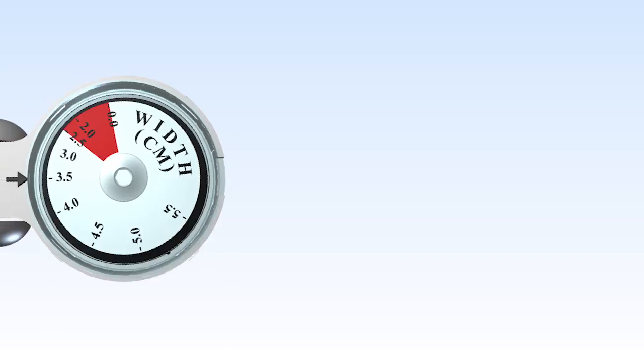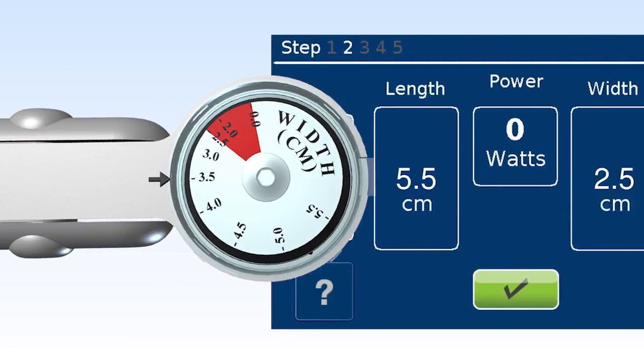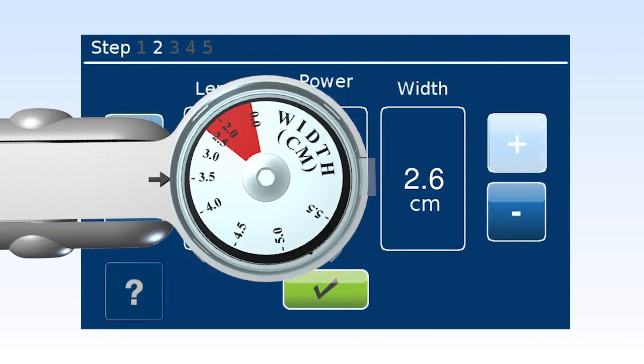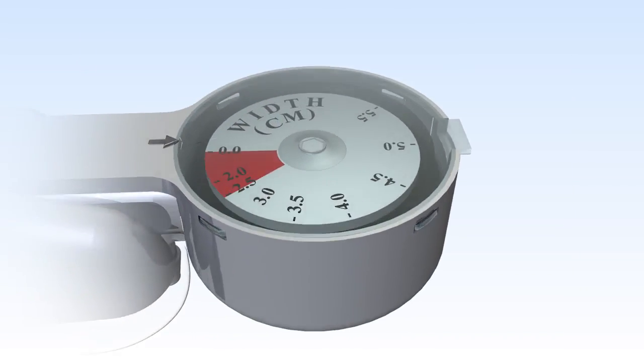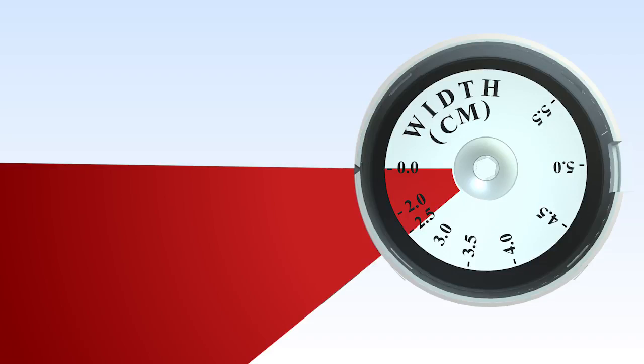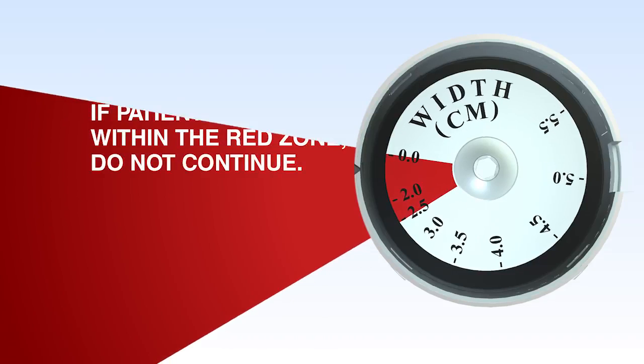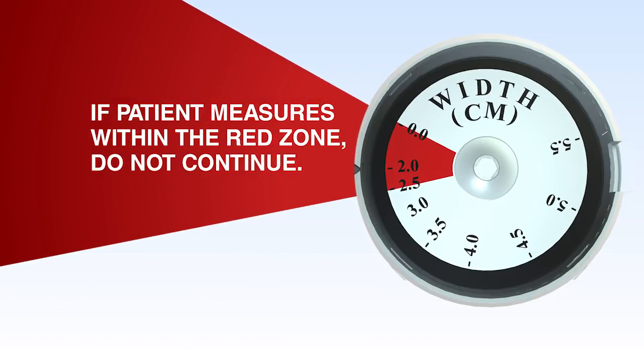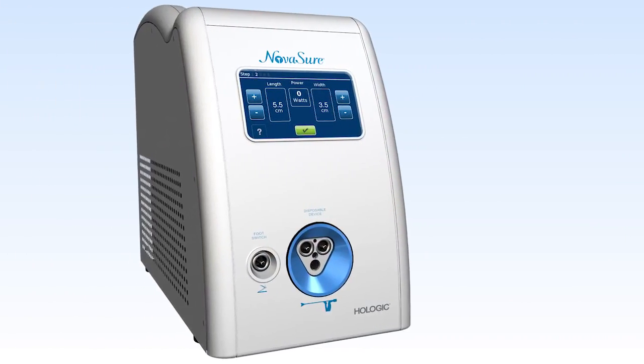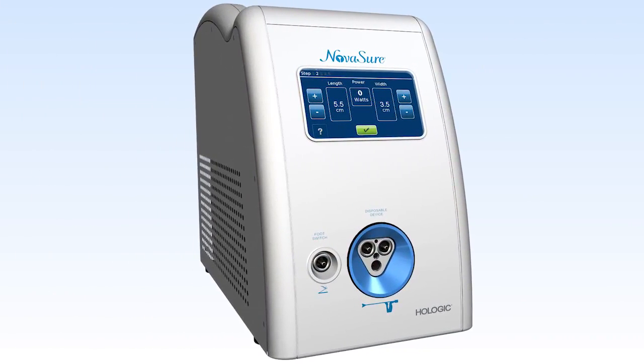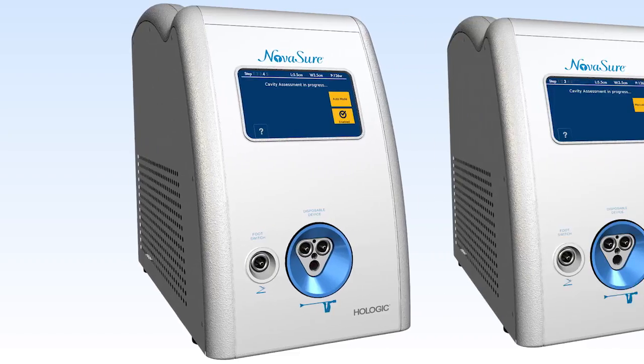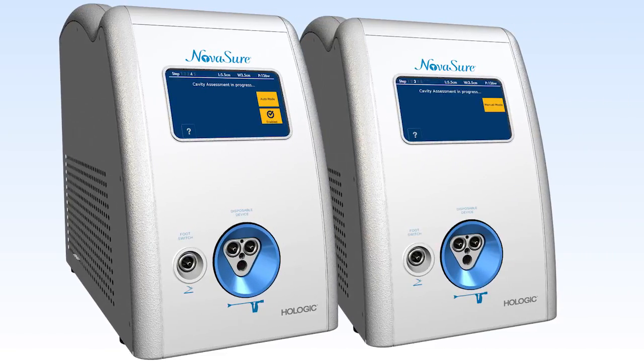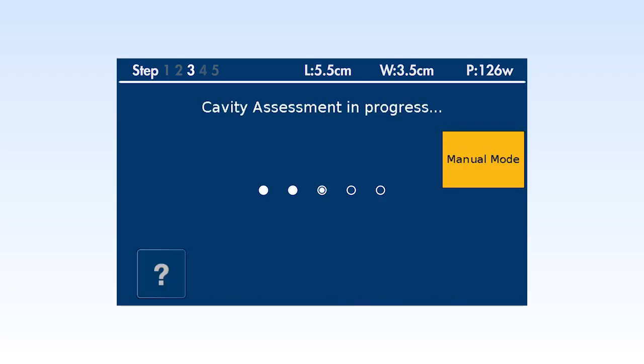Input the value shown on the width dial indicator into the NovaSure RF controller width setting by depressing the plus and minus symbols. The width of the cavity should be at least 2.5 centimeters. Patients with a cavity width of less than 2.5 centimeters are contraindicated and should not be treated with the NovaSure device. The NovaSure RF controller can be operated in two different modes, automatic mode and manual mode. For this procedure, the controller has been set to manual mode.